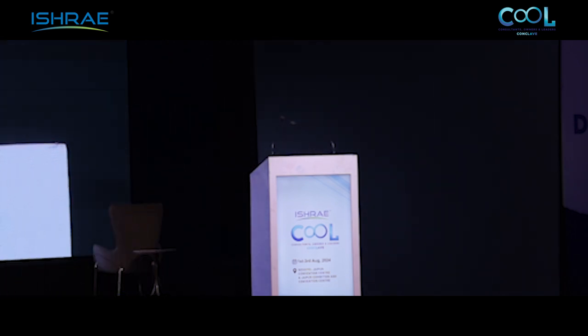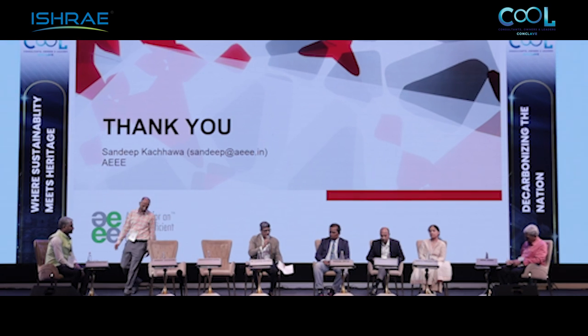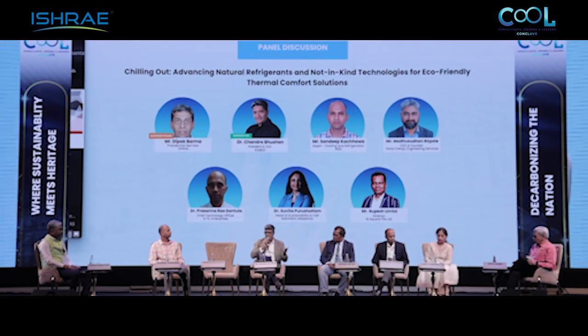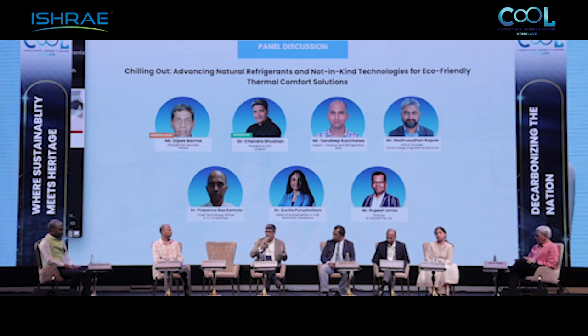Thank you. I think the biggest challenge with the India Cooling Action Plan is how do you convert it into a state cooling action plan and then a city cooling action plan. The cooling action plan has not gone to the states and cities, and therefore the achievement has not been significant. The other issue is that at a temperature of 50 degrees, we saw how vapor compression technology was failing in Delhi. So I think we also have to look at not only the impact of higher temperature on the upcoming technology, but also on existing technology.